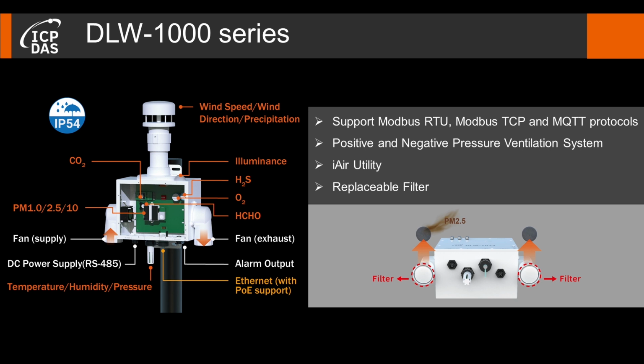The module supports various protocols including Modbus RTU, Modbus TCP, and MQTT protocols. The DLW-1000 series adopts positive and negative pressure ventilation systems. The active ventilation system creates a difference in air pressure between the space inside the module and the environment that surrounds the module. The turbulent and evenly mixed airflow produced improves the accuracy of the obtained values. In addition, the DLW-1000 series provides IP54 protective design and replacement filters. It allows the module to be used in extreme environments. As for regular maintenance, clients can replace the filter patch themselves to save time and cost.